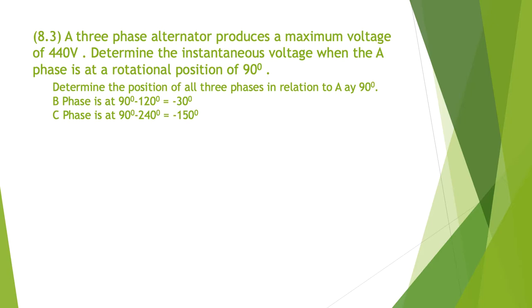Determine the position of all three phases in relation to A phase at 90 degrees. B phase is going to be at 90 minus 120, so it's going to be at minus 30. C phase is going to be at 90 degrees minus 240, that's going to be minus 150.